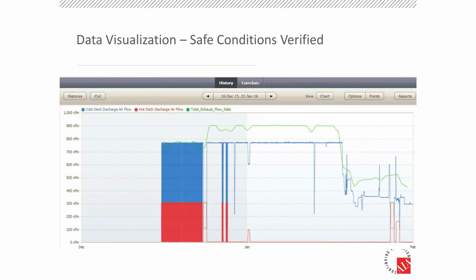The next thing we're concerned about in a lab is safety, really the primary thing. We visited that next, and you can see how we can add exhaust flow to this same graph and look at it on a time series basis, seeing that our exhaust flow is always above our supply flow. All of these labs needed to maintain a negative pressure, so we could verify that. Looking at the time series data, the human brain likes to see it in that format.